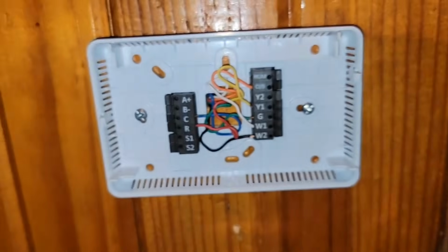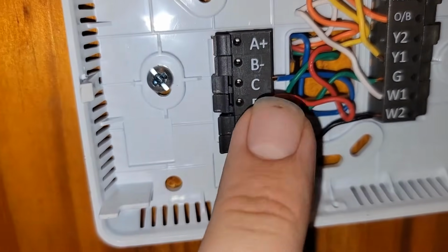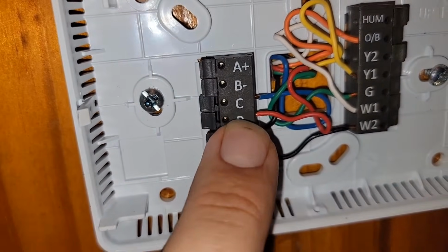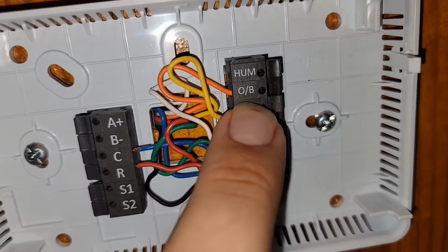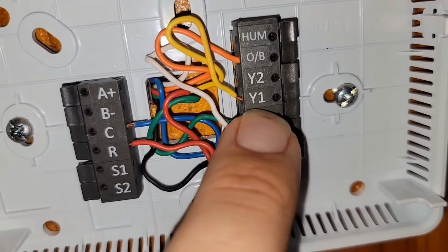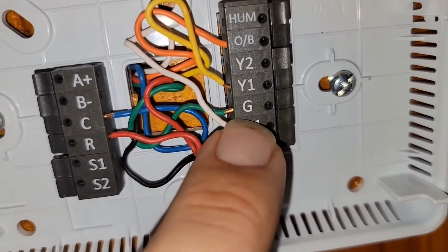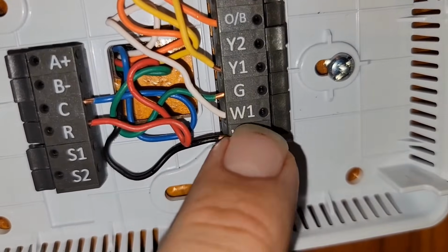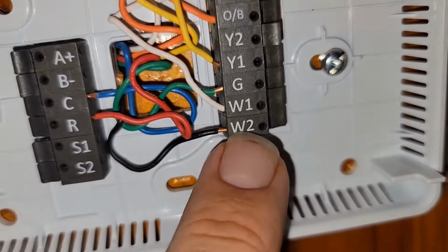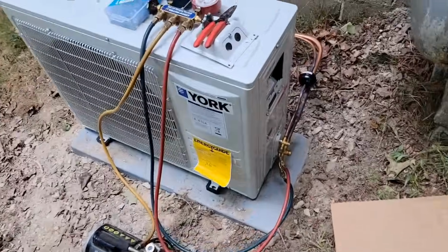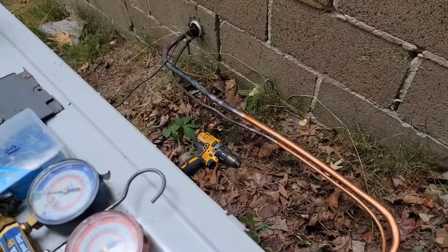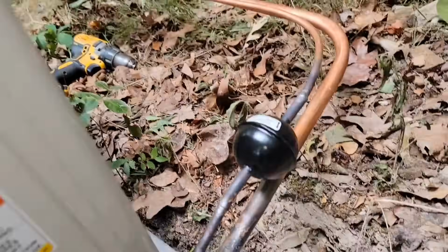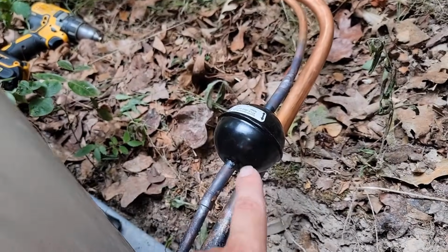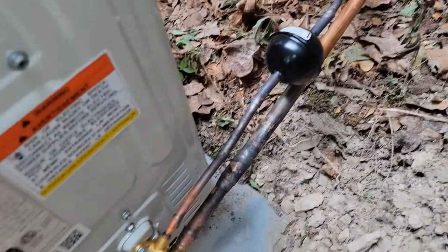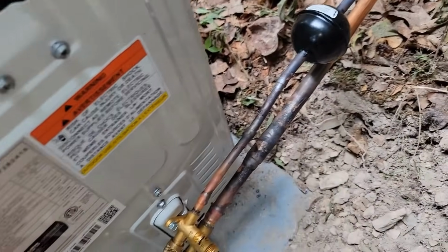Let's look at the wiring for the thermostat. We've got our R and our C, our 24 volts, red, common. We got our O for reversing valve, our first stage cooling, Y1, our fan, G, and our W1 and W2 hooked up. All right, got the refrigerant lines piped in. It looks pretty good. Got the filter dryer installed. It's a bi-flow, so it doesn't matter what direction the arrow points as far as the installing of that filter dryer.